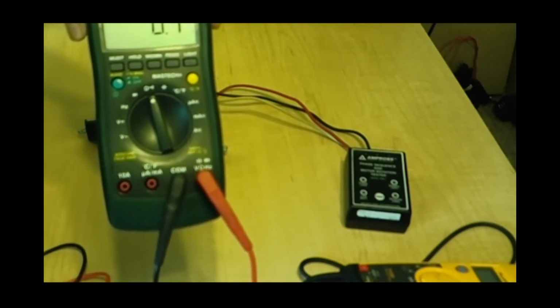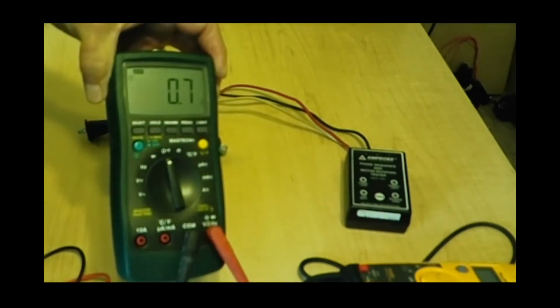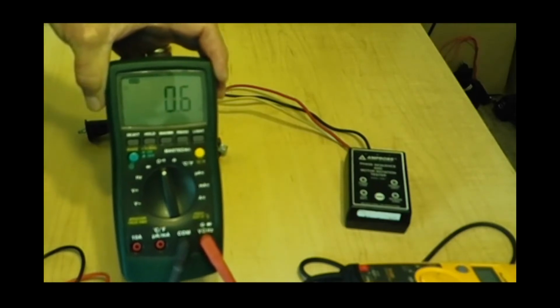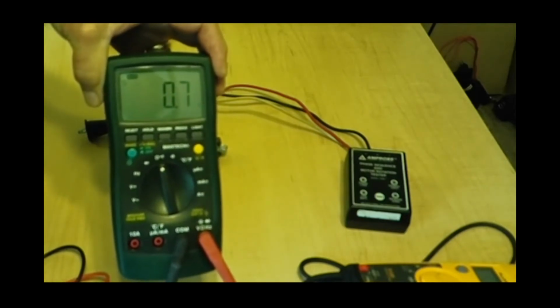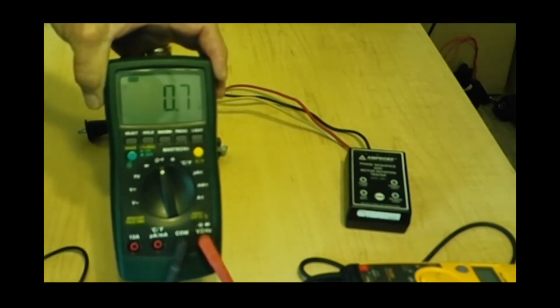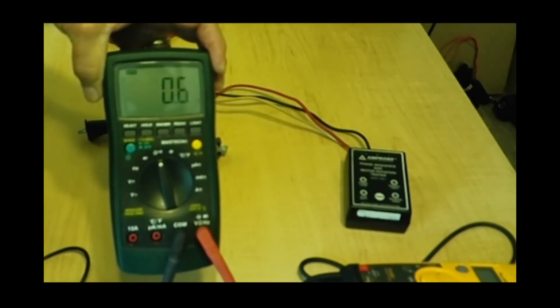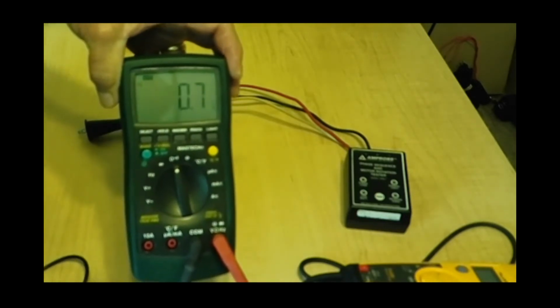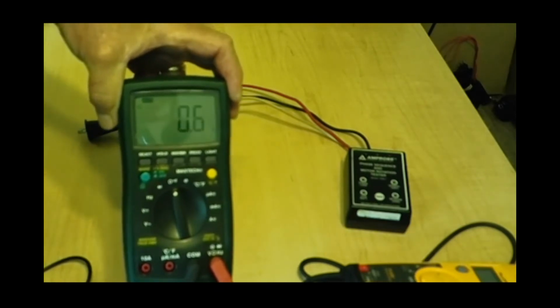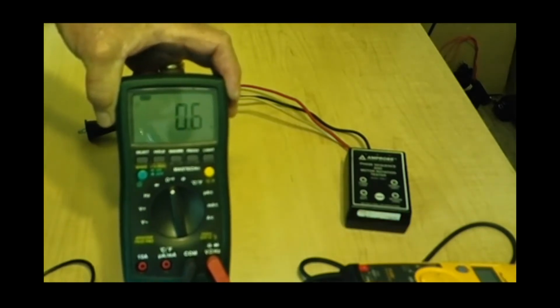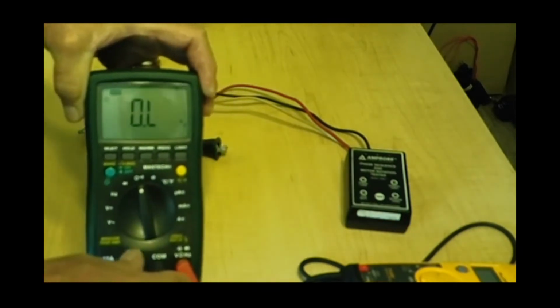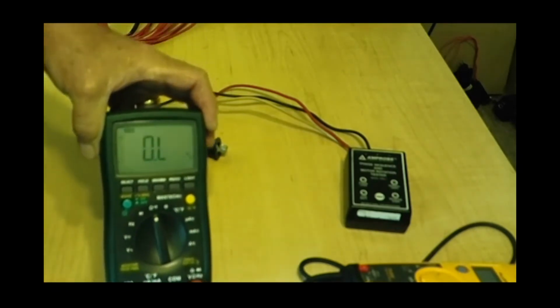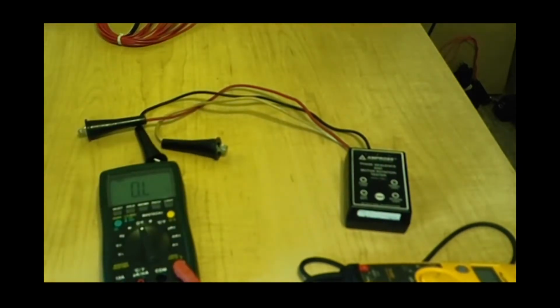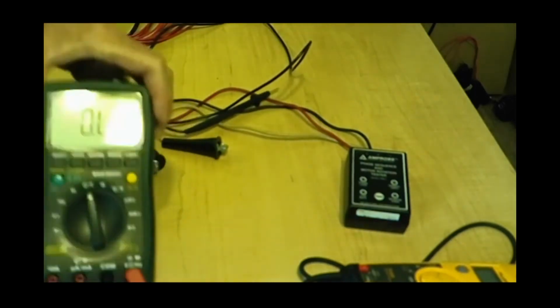Well, the problem here is this number we're seeing, this 0.7 on the test leads, 0.6, 0.7, is going to affect every single measurement we take. So test leads are disposable. It is recommended that you remove, throw away and replace the test leads when they reach 0.5 ohms or more. Now, to find out which test leads are bad and which are good is a simple process.